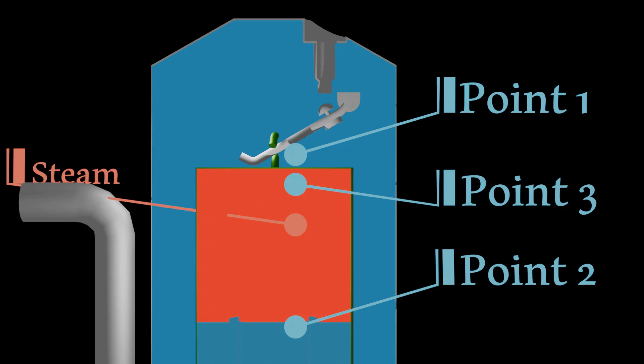But this time, rho is the density of steam, which is much less than the density of water. The resultant force of these two pressures will create a force that acts in the upward direction, depending on the amount of steam in the bucket.